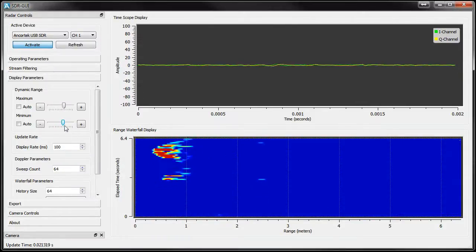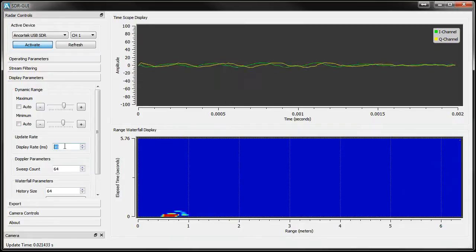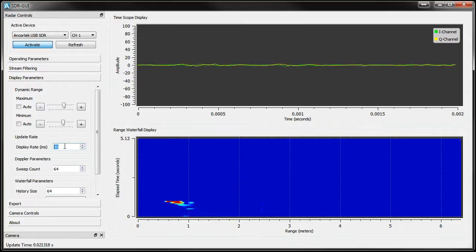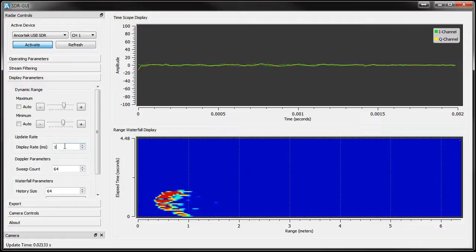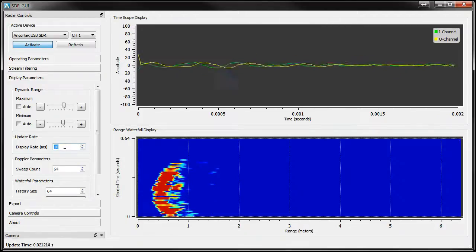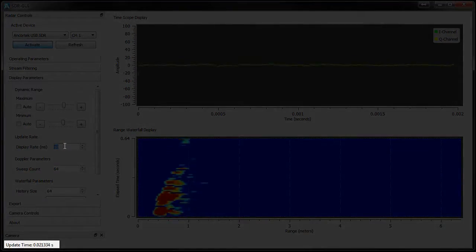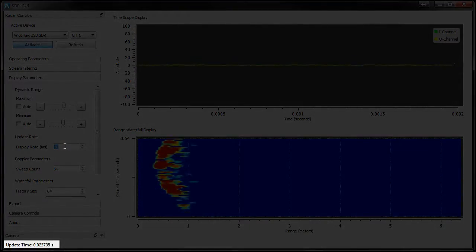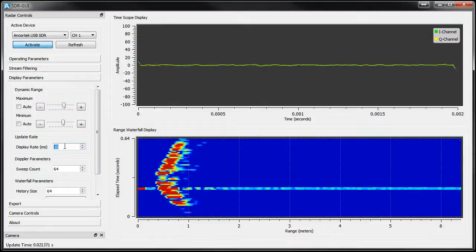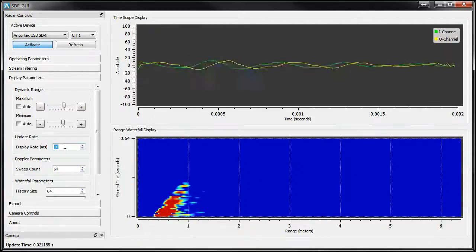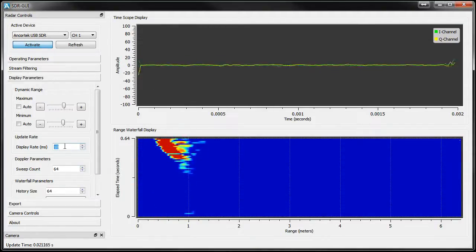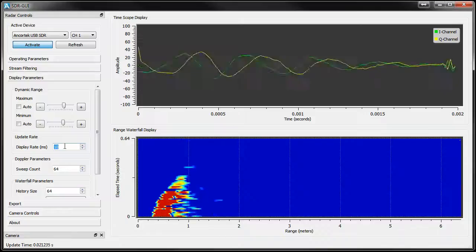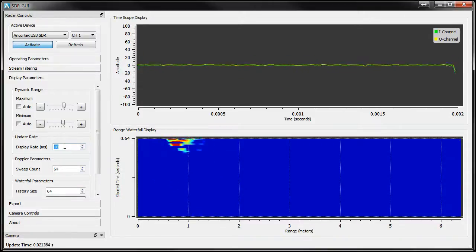Below this is the Update Rate Control, which sets the desired screen update rate. It's important to note the Update Time note on the bottom of the screen. This displays a summation of how long it takes the GUI to finish one complete data cycle. In other words, how long it takes to grab a sweep, process the sweep, and update the display.